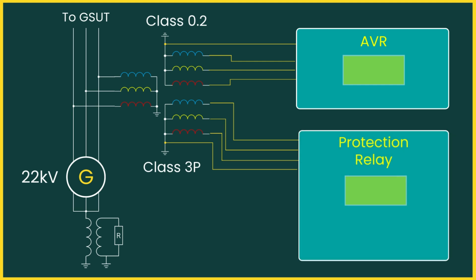During a routine test, the AVR setpoint was increased to 105%, perfectly within generator capability. When the machine reached about 22.9 kV, it tripped on overflux protection. The fault record showed the protection relay saw 23.3 kV. The first reaction on site was predictable. Something must be wrong with the relay. Then the suspicion moved to the AVR. Then to the PT ratio. Then to wiring. Everything was healthy.